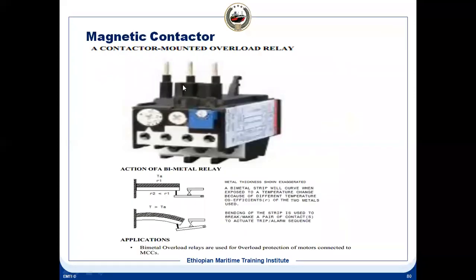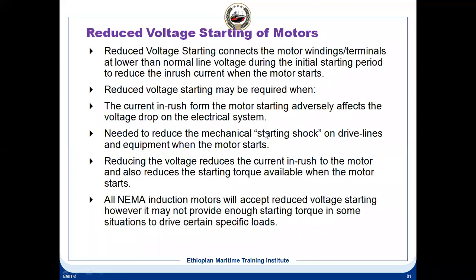Then this is a magnetic contactor with an overload relay. We will see the different types of overload relays in the coming slides. Now the next one is the reduced voltage starters. Reduced voltage starters are the star delta starters. We are reducing the voltage during starting so that the starting current can be controlled.